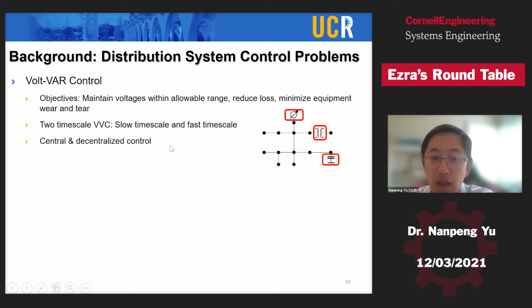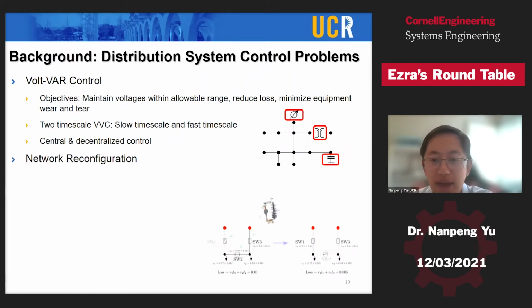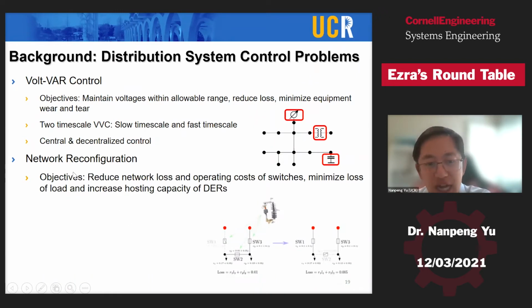Many researchers develop centralized and decentralized control for Volt-VAR control. And the second type of control problem that a lot of people look at is network reconfiguration. So the example is shown here where we have two distribution feeders represented by these two red dots, and they're serving two loads. And I have three branches here and three switches. By changing, for example, opening switch 1 here in scenario 1, opening switch 2 and closing switch 1 in scenario 2, we have different amounts of losses and different voltage profiles. So again, the objective of the network reconfiguration is to change the status of these switches so that we can reduce the network losses and the operating cost of the switch and minimize the loss of load, or even potentially increase the hosting capacity of distributed energy resources.